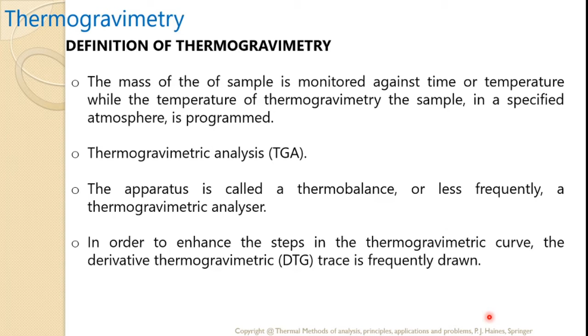It should be recognized that several manufacturers prefer to call this technique a thermogravimetric technique. That is why thermogravimetric analysis is abbreviated as TGA. The apparatus is generally called a thermobalance, or less frequently a thermogravimetric analyzer. In order to enhance the steps in the thermogravimetric curve, the derivative thermogravimetric curve, that is DTG, is frequently drawn.